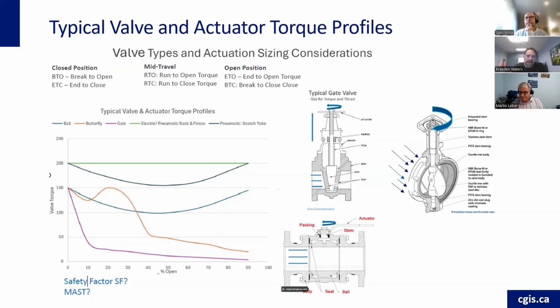Right. And I guess there's the consideration of duty cycle, especially when it comes to your run torque. With a lot of actuators, the break torque is required for a fairly short period of time. But with a plug valve or a ball valve, where you have that higher torque profile requirement, your duty cycle needs to be considered as well, to make sure that the opening and closing times aren't going to exceed the duty cycle. So, really good question.